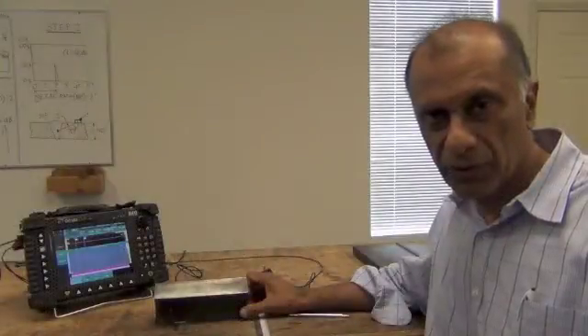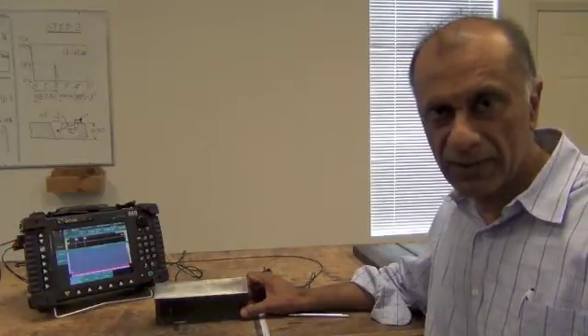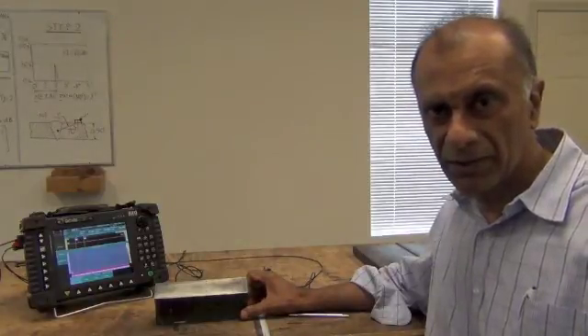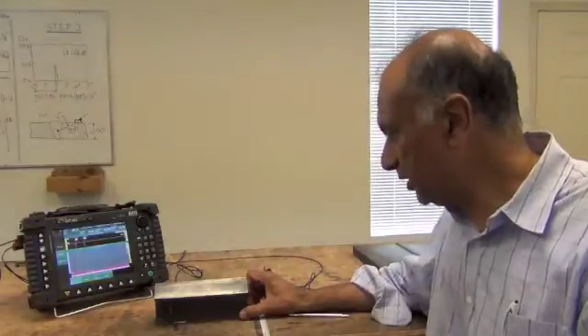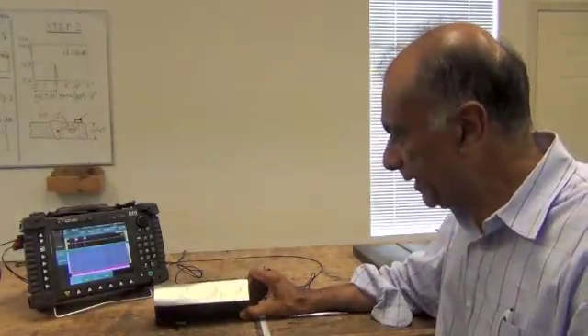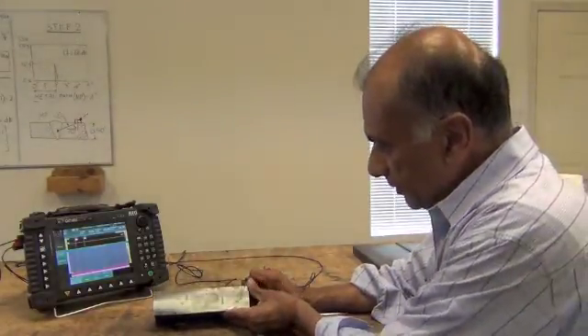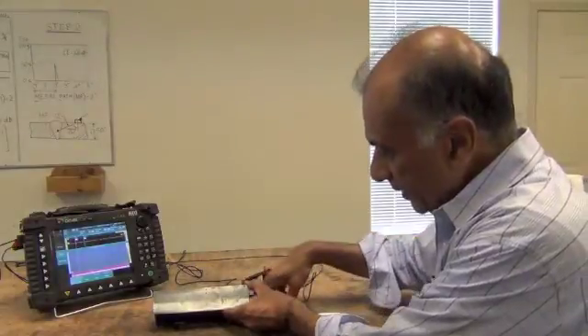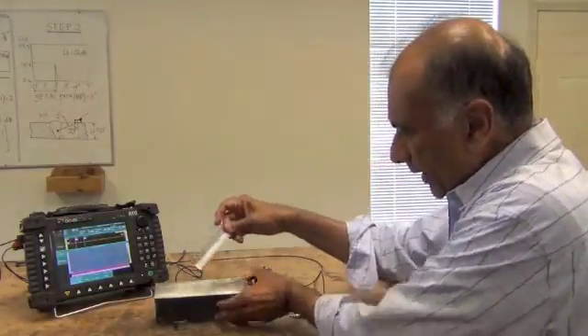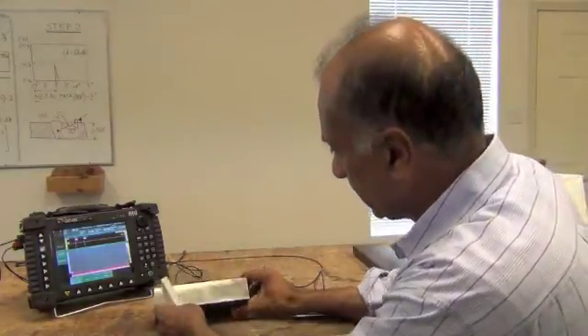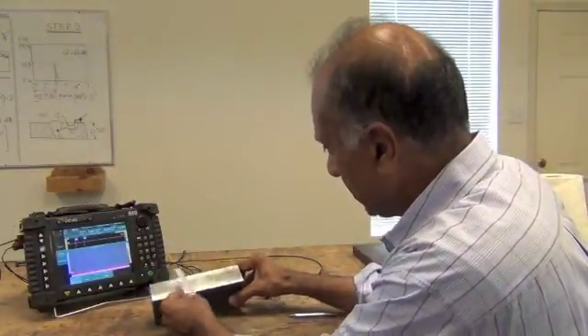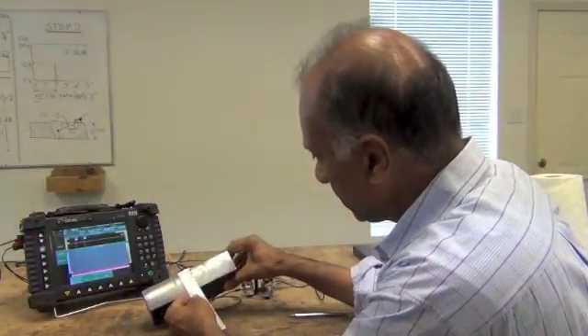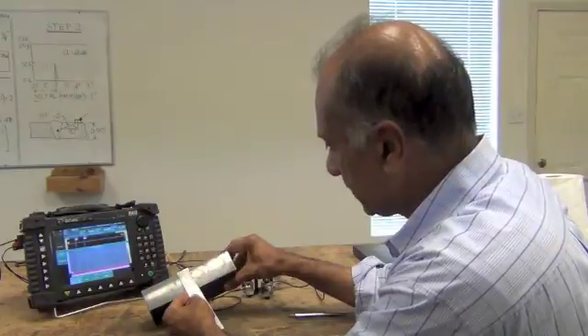We will now go through the TOFD calibration process. Here is a TOFD calibration block which is cut off from a pipe. You can see there are holes drilled in the calibration block, and holes in this block are actually at 4mm, 10mm, and about 21mm.